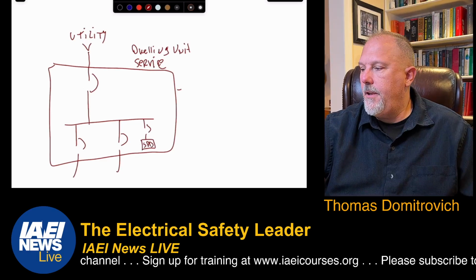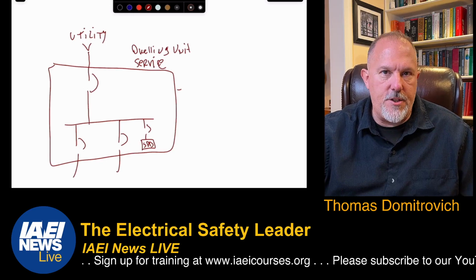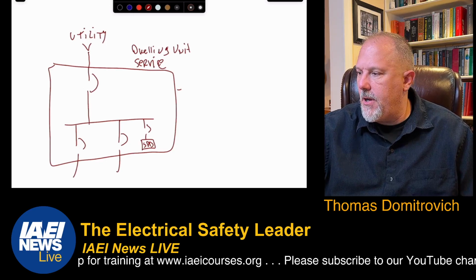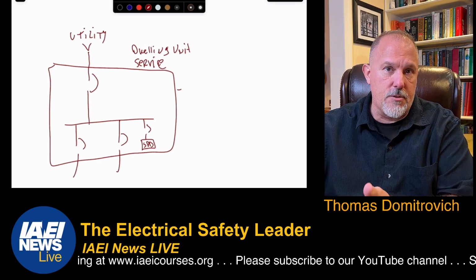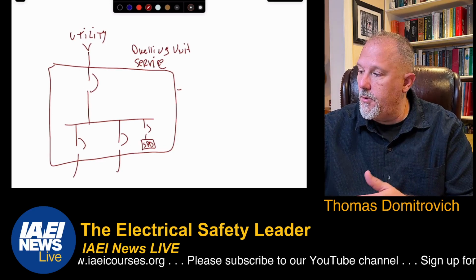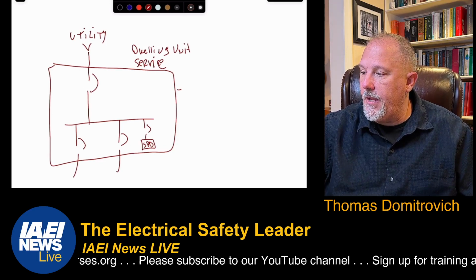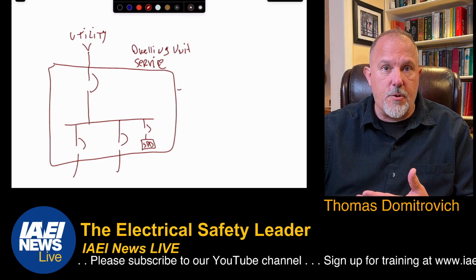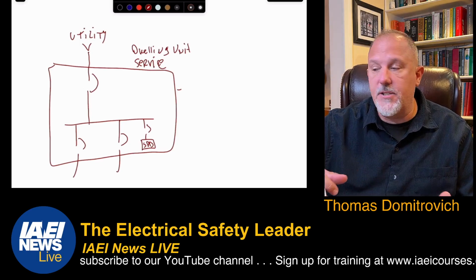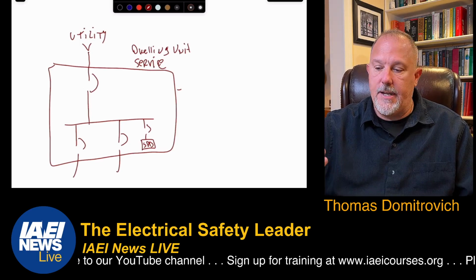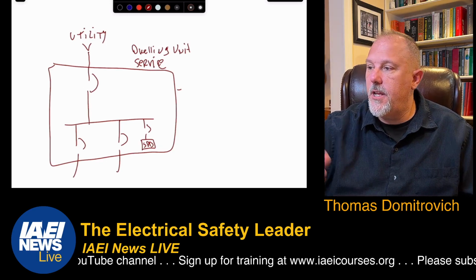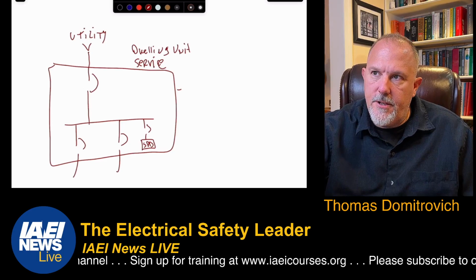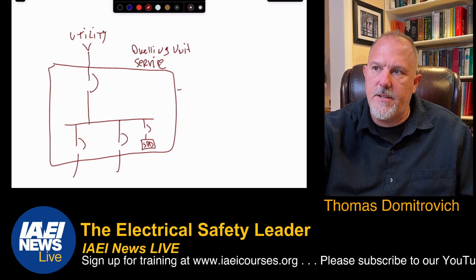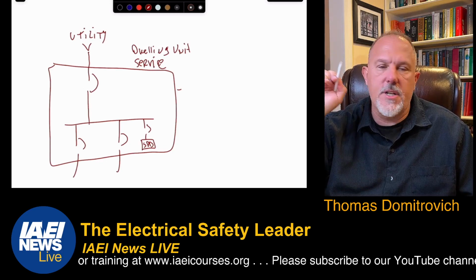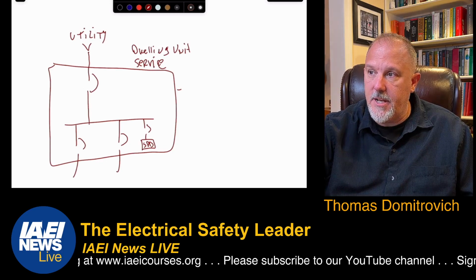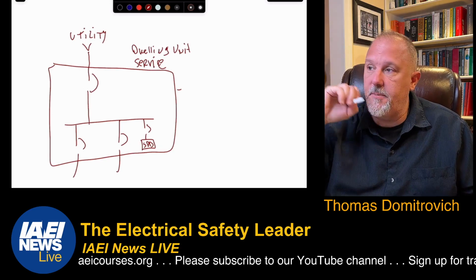So you can accomplish that various ways. You could put a breaker in the box. You could buy a panel board that has it built onto the bus. You can buy a surge device, connect it through a breaker, and put it on the outside. You can have a surge protective device that doubles as a circuit breaker as well. It does two jobs, and you plug that right onto the bus. Or you can buy a surge protective device that plugs right onto the bus. So now we had surge requirements for every service, and then in the 2023 cycle, they expanded to dormitory units, guest rooms and guest suites of hotels and motels, and areas of nursing homes and limited care facilities used exclusively as patient sleeping rooms.